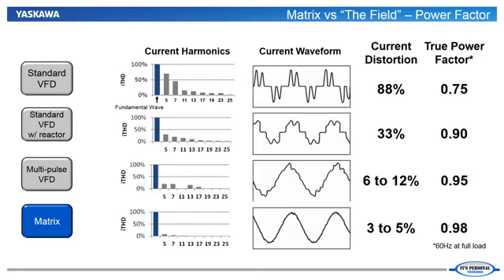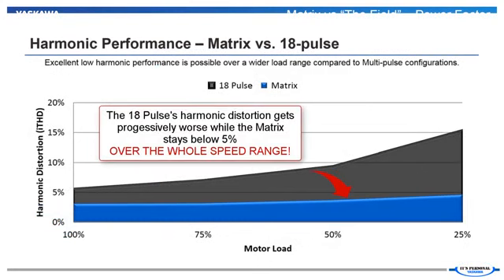The matrix drive can operate at full load with less than 5% total harmonic current distortion. Even an 18-pulse VFD won't necessarily meet 5% total harmonic current distortion at its input.